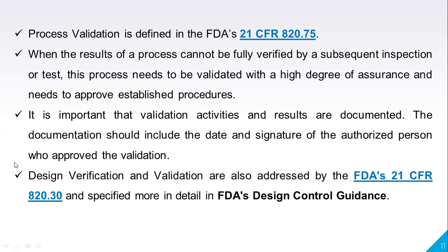Okay. So that is the date and signature we have to include in that report. Apart from that, design verification and validation are also addressed by the FDA's 21 CFR 820.30. Not only 820.75, 820.30 also mentions design verification and validation. 820.75 shows how important process validation is, whereas 21 CFR 820.30 explains design verification and validation. Right, clear? Yes, sir.